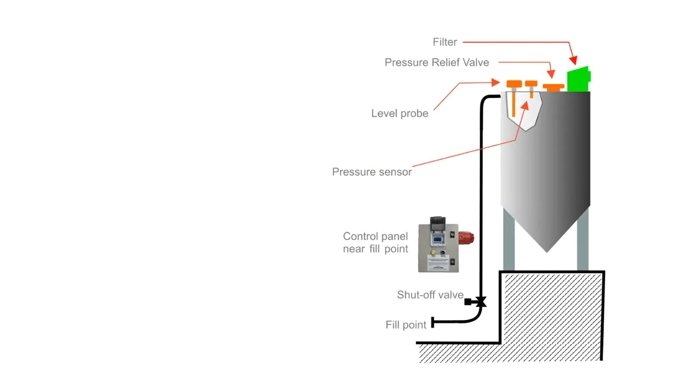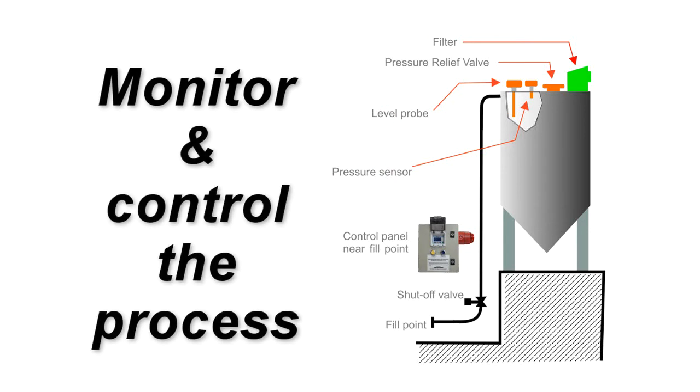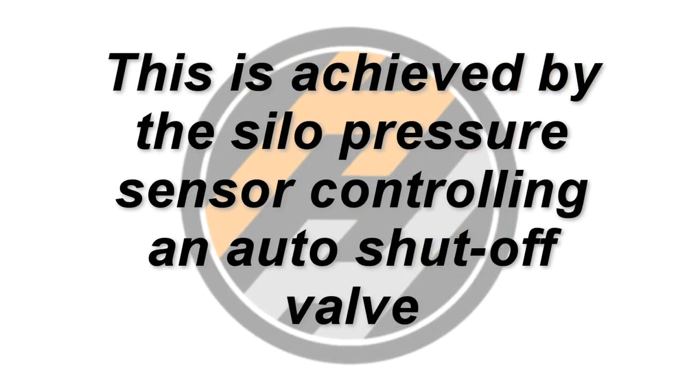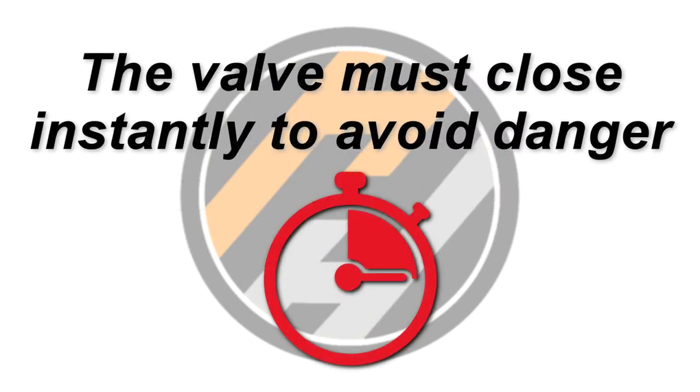The first step in eliminating this risk is to install a silo protection system that monitors and controls the process. The core of this system should be a sensor monitoring the pressure inside the silo, rather than at the fill point. The system must be able to automatically take control and close the inlet valve if the pressure becomes dangerous. This needs to be done automatically as the valve must close instantly.